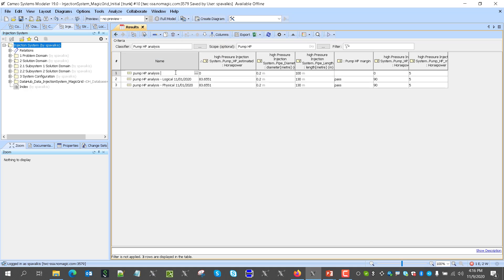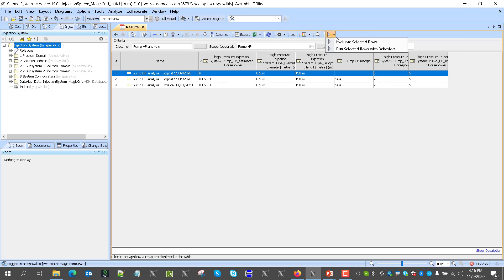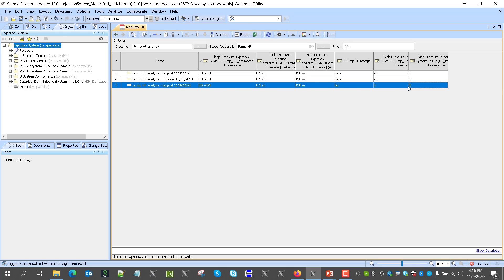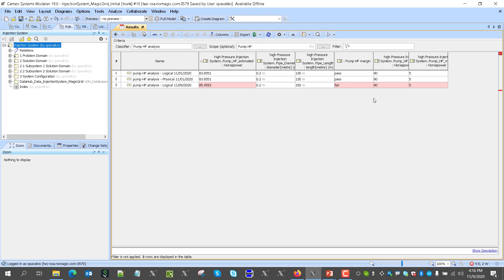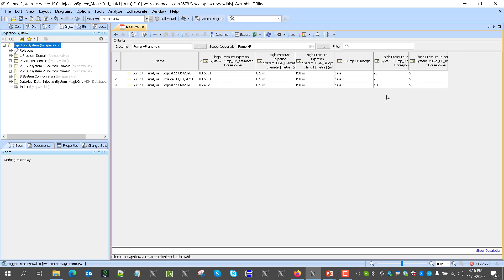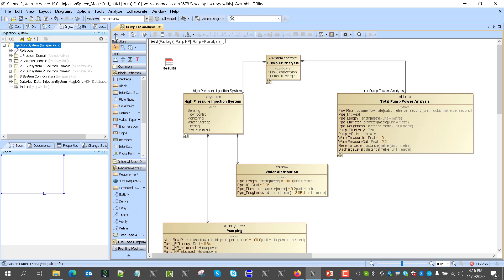Now we'll create at least one new configuration and enter the new pipe length. This parametric model is existing and we run through this configuration — it could also come from some external source. We run through this configuration and get that it failed. So at 90 horsepower it still fails. Next pump: increment 10% — 10 horsepower more — and we see that this is passed. So we have a 100-horsepower pump. Let's go and update the system requirement based on that.